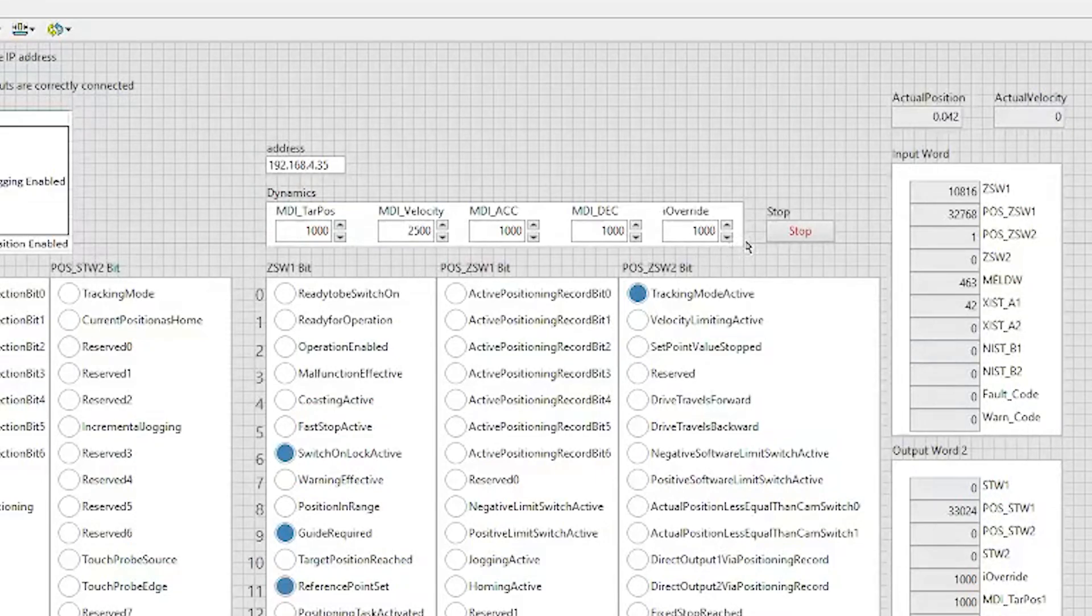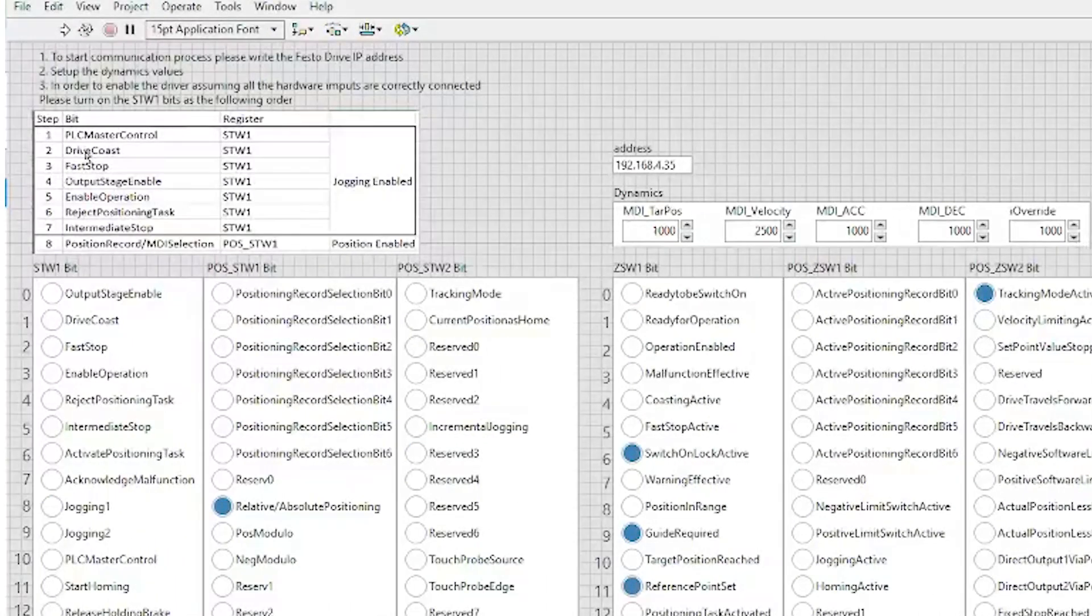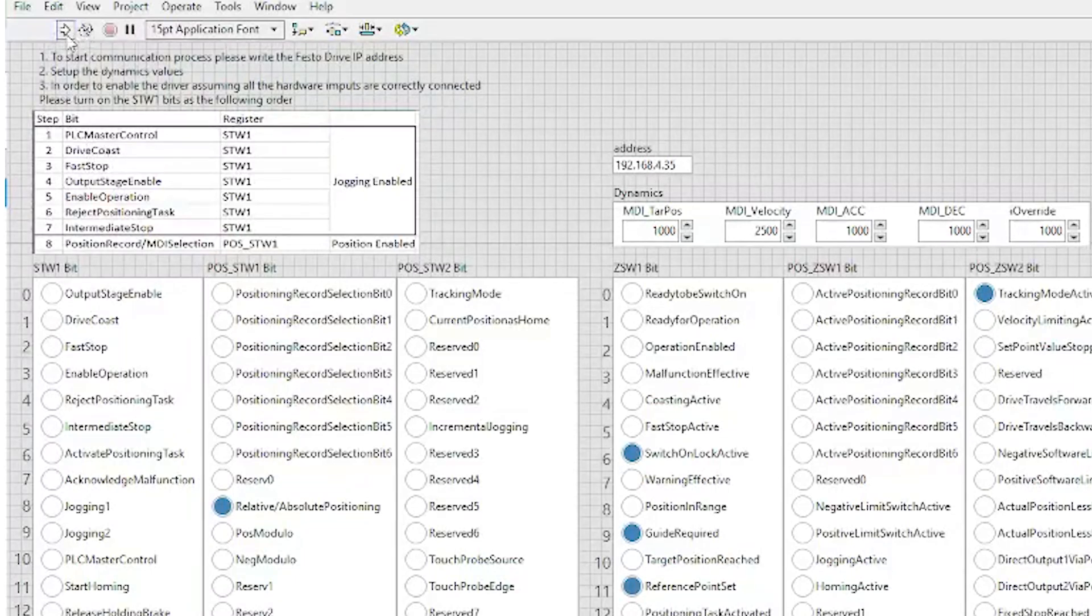You'll notice on the left hand side is the proper procedure for starting up the drive. First we need to enable the actual project, next we'll do the PLC master control, then the drive coast. As you'll notice, the bits on the right hand side are now activating because we're being able to read the values from the drive.